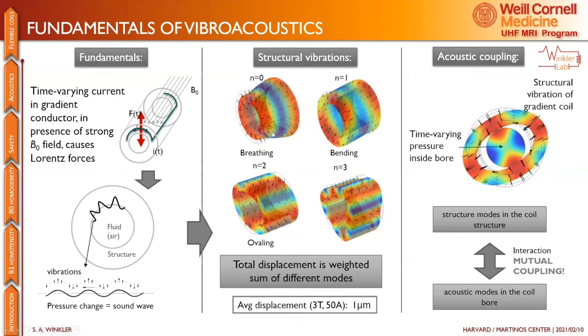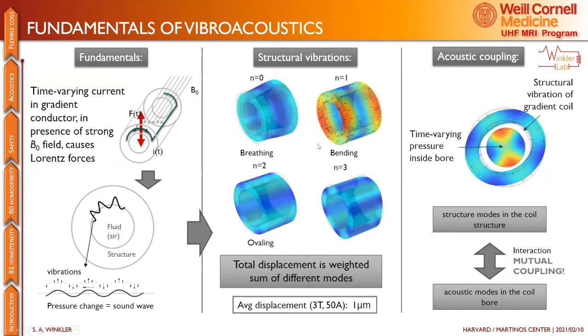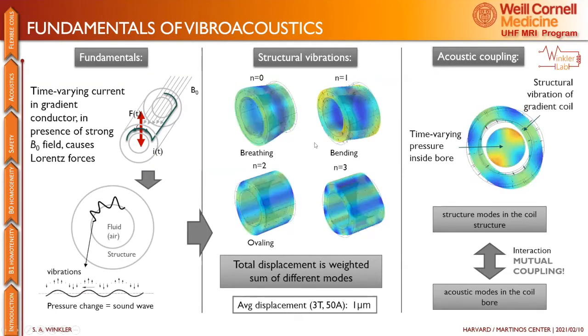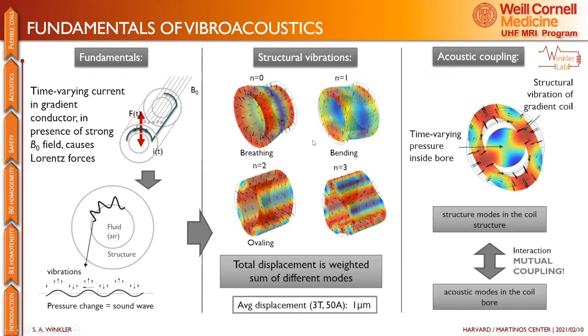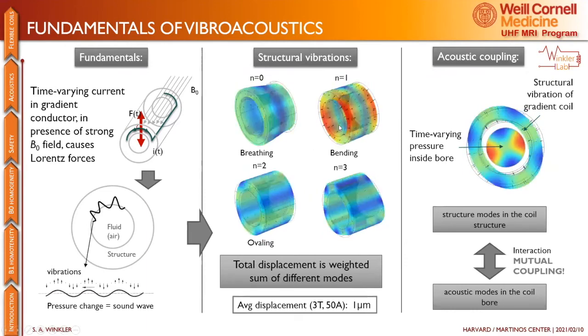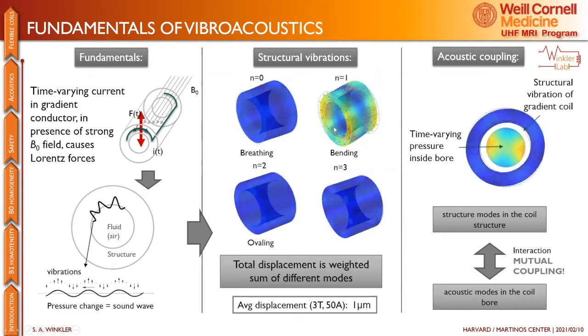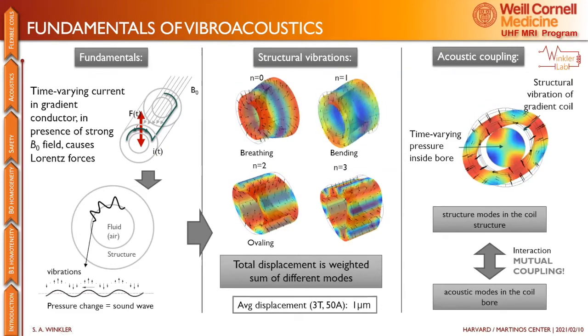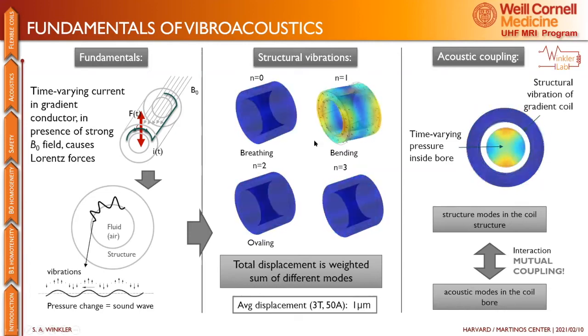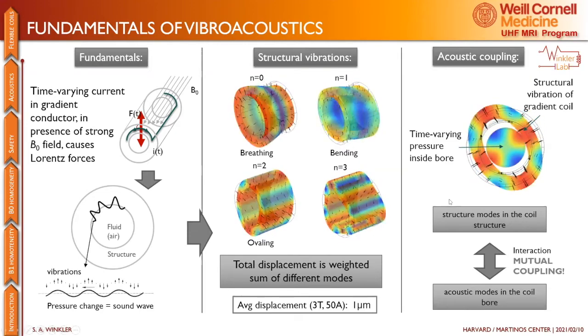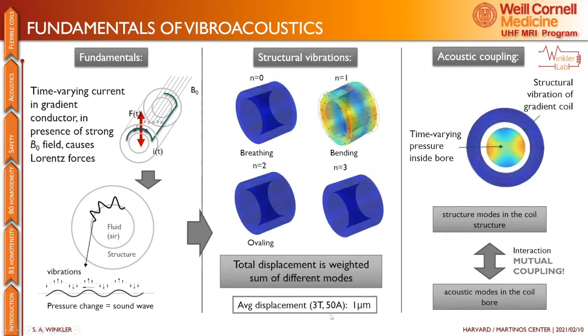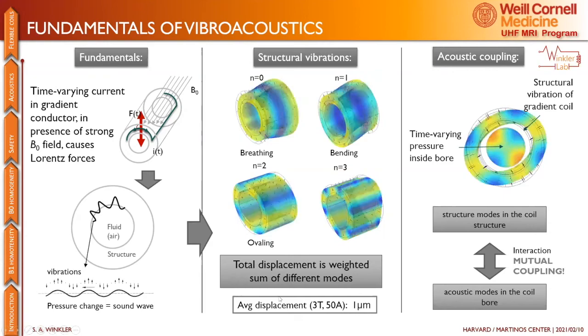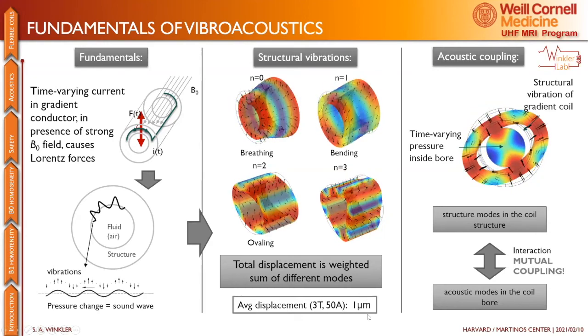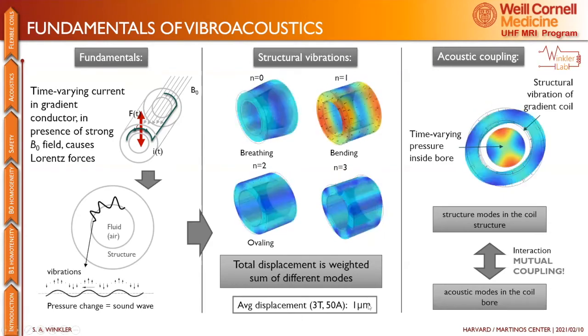I always show this slide because it's colorful and wakes people up a bit, because my talks are long, you know. You can quantify these vibrations by creating a weighted sum of different modes. There are breathing modes, bending modes, ovaling modes, and so on. The average displacement for 3T and 50 amps, with a more versatile coil, not so much the head gradient coil, is about 1 micron.